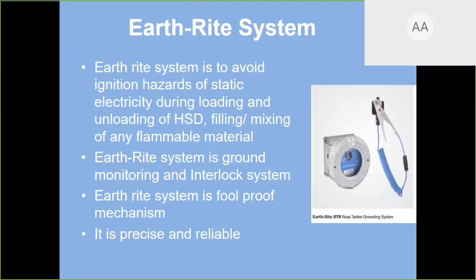The Earth-Rite system is a ground monitoring and interlock system. It is a foolproof mechanism. Why is it foolproof? With the Earth-Rite system, if the earthing continuity is 100% correct, then only your pump will start. Otherwise, the pump will not start. You have done earthing manually, but whether earthing continuity is there or not, you will not check, because somebody has done paint, and on that you put a clip. You assume that earthing has been done, but actually it is not done. So the Earth-Rite system will ensure there is earthing continuity and the static charge goes to earth and there is no spark, and then only the system will run, otherwise it will not run.